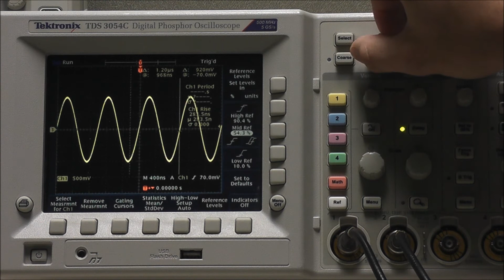Selecting reference levels, we can set our levels in percents or units. We can also change our high and low references for measurements like rise time, and we can change our middle references for measurements like period. Note that we must select which reference we want to change before using the multi-purpose control. We can also select Set to Defaults to restore any changes made to those reference levels.